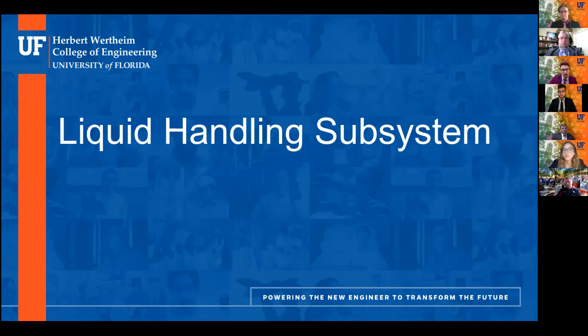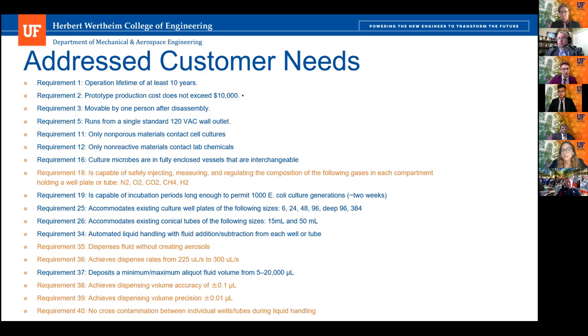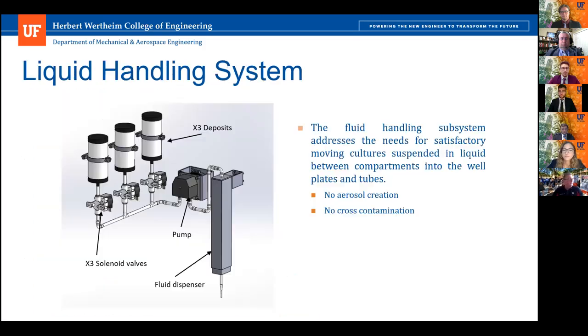My name is Irate and today I'll be explaining the fluid handling system, which includes the liquid handling system and the air injection. The customer needs related to this subsystem include the ability to inject, measure, and regulate the composition of five different gases; the ability to dispense fluid without creating aerosols and avoiding cross-contamination; as well as a flow rate between 225 to 300 microliters per second, with the highest accuracy. The liquid handling system is responsible for providing nutrients to cultures. The system consists of three deposits, three solenoid valves, fluid handling dispensing valves, and a pump.